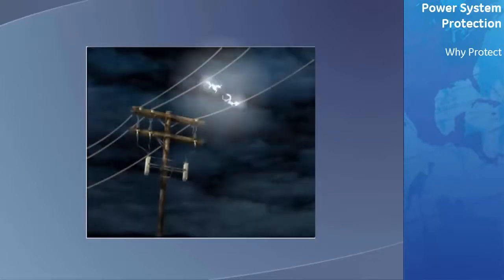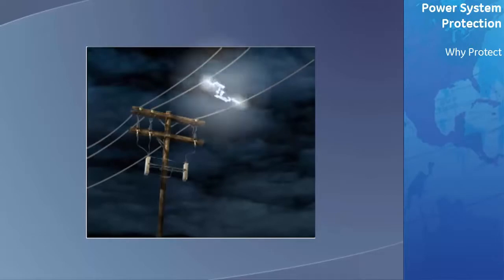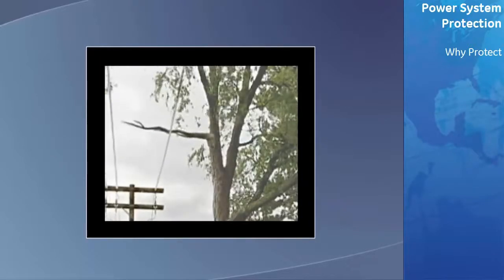Lightning striking the transmission line, or a strong wind causing two phases of the transmission line to touch and form an arc, are common causes of an intermittent fault to an overhead transmission line. The resulting arc ionizes the air and turns it into a conductor, and the arc is then maintained by the power in the line. In both cases, the protection system responds by removing power from the line for a period of time long enough to allow the ionized air to dissipate, and then reapplies power to restore service.